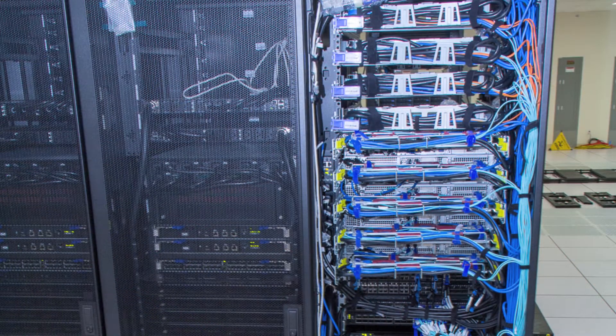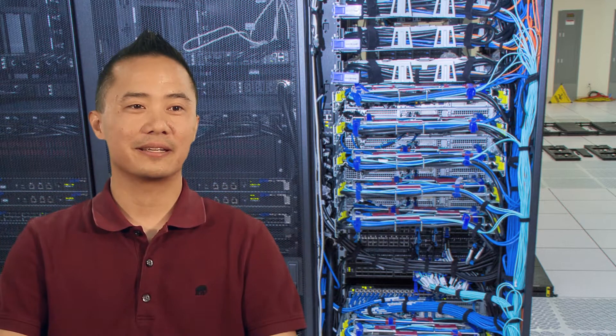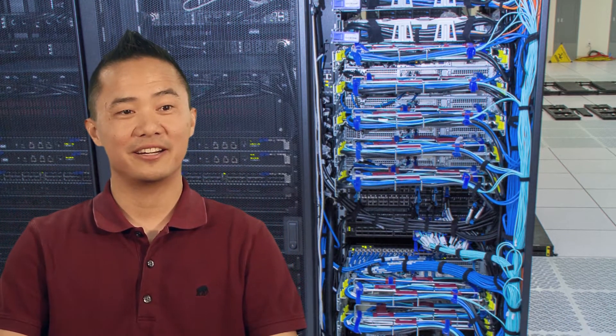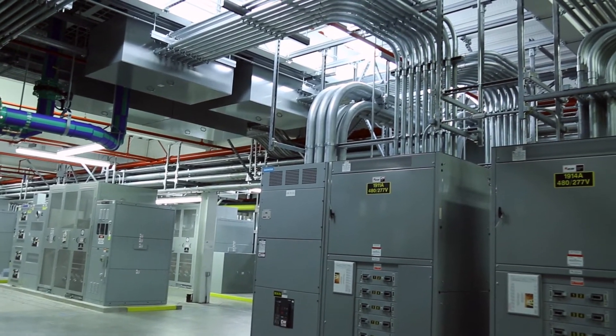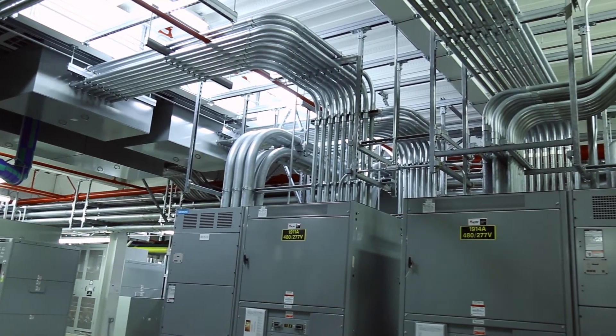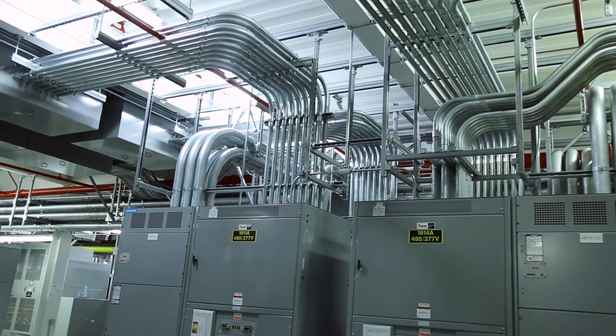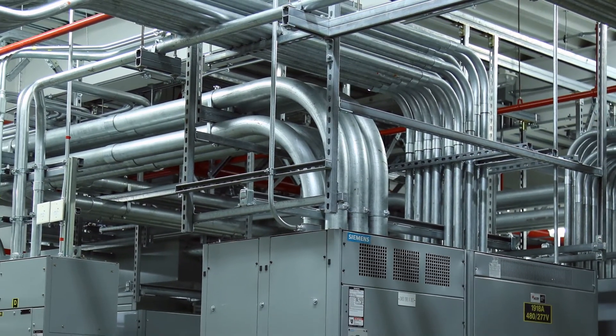What's unique for Sierra is that the racks are very dense, so we need to have a lot of power for a small amount of area. We spent two years on a modernization project prior to Sierra's installation to upgrade our infrastructure, bringing in higher voltage to the bottom floor and saving on conduit and conductor costs.